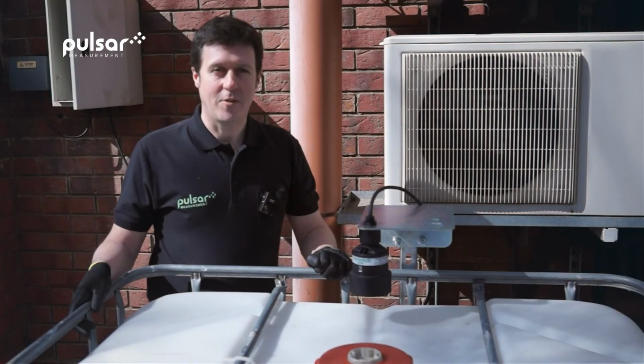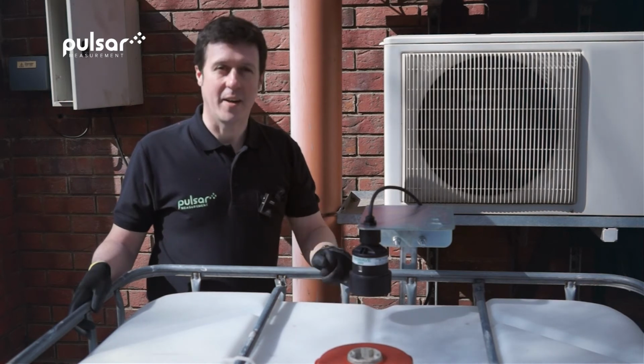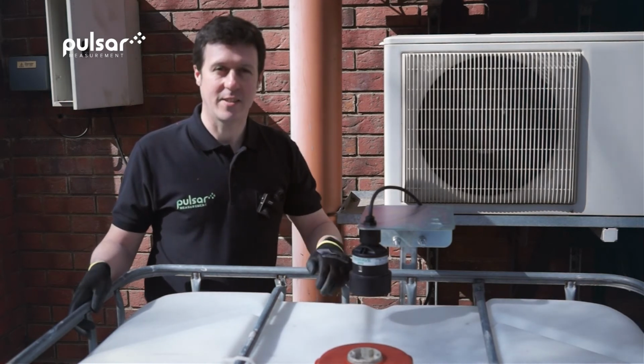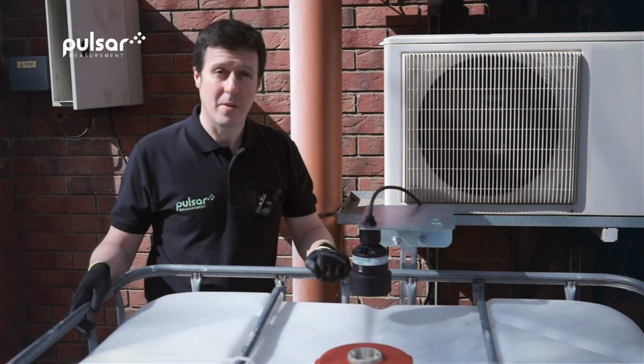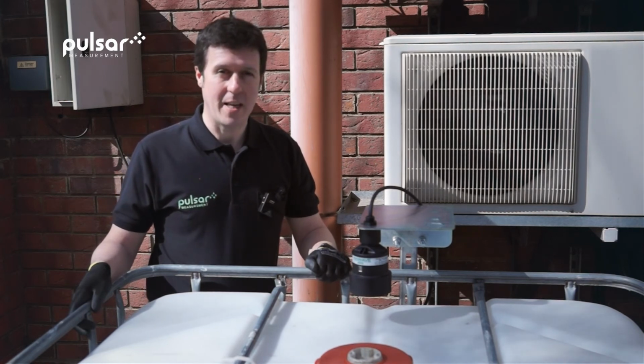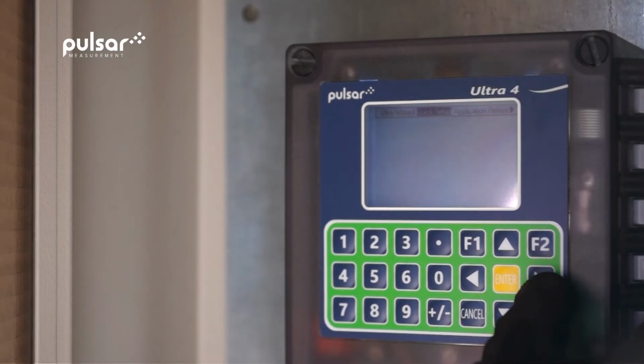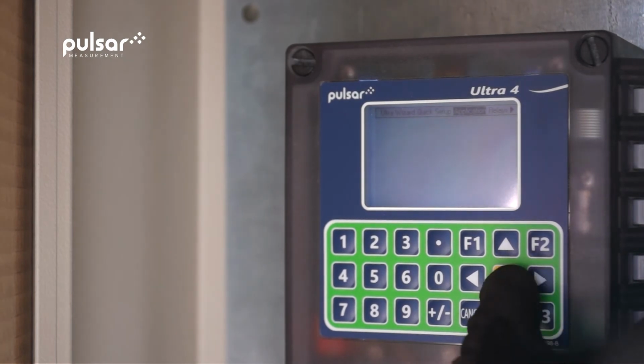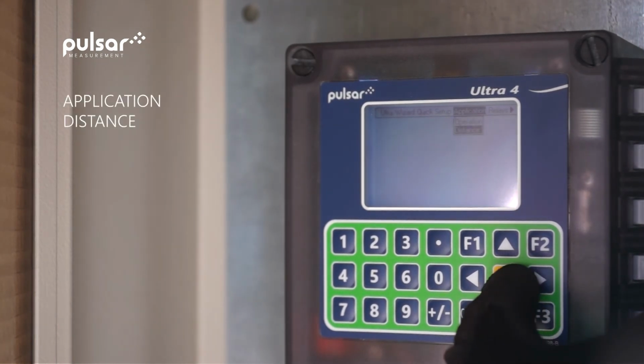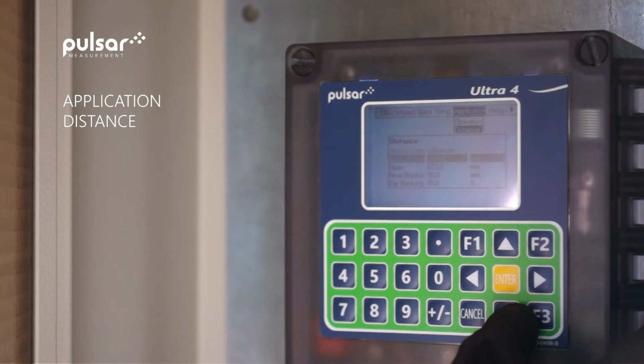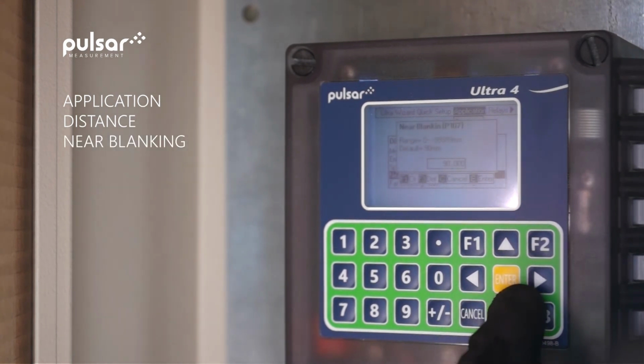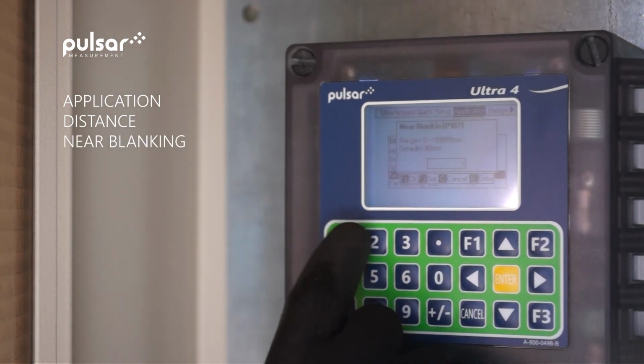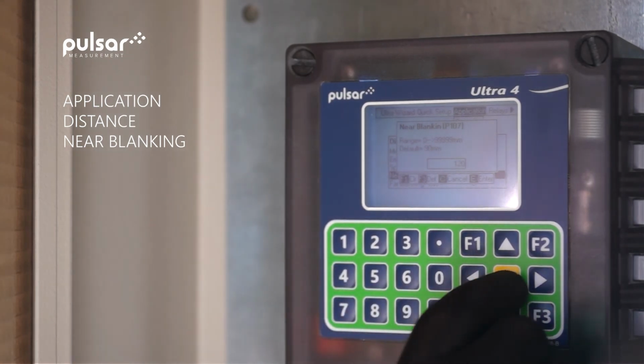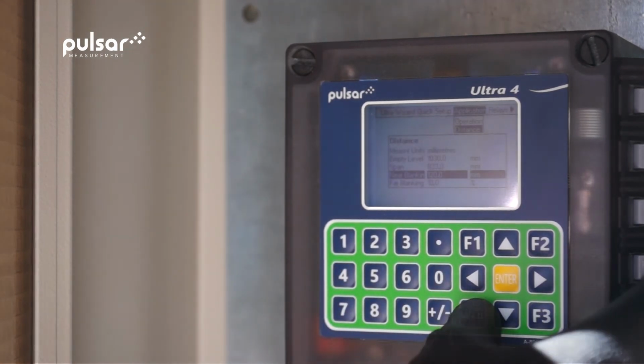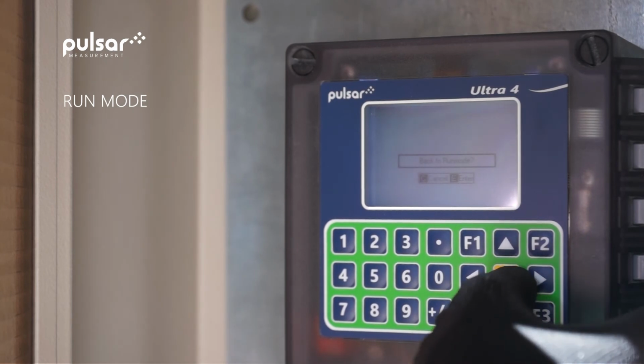As we're using the radar transducer to shoot through the top of the tank, we need to take into account the signal from the top of the tank itself. We can easily do this by increasing the near blanking distance. The near blanking can be adjusted by going to the application menu and the distances submenu. We can scroll down to near blanking, enter our new value, which will be 120 millimeters. Now we can return to run mode.